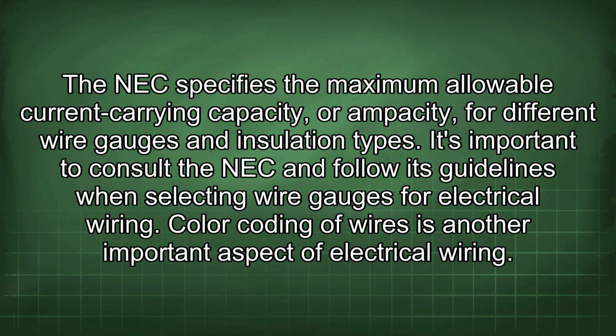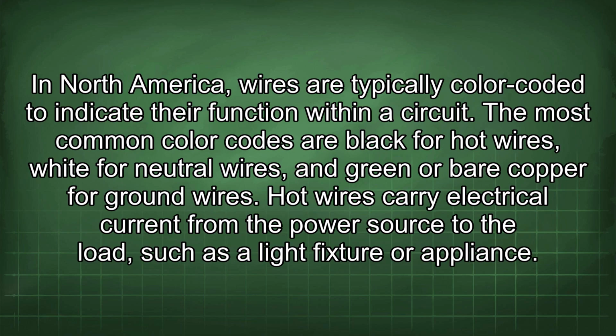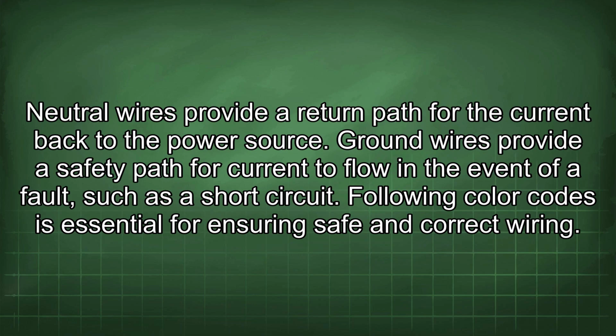Color coding of wires is another important aspect of electrical wiring. In North America, wires are typically color-coded to indicate their function within a circuit. The most common color codes are black for hot wires, white for neutral wires, and green or bare copper for ground wires. Hot wires carry electrical current from the power source to the load, such as a light fixture or appliance. Neutral wires provide a return path for the current back to the power source. Ground wires provide a safety path for current to flow in the event of a fault, such as a short circuit. Following color codes is essential for ensuring safe and correct wiring.